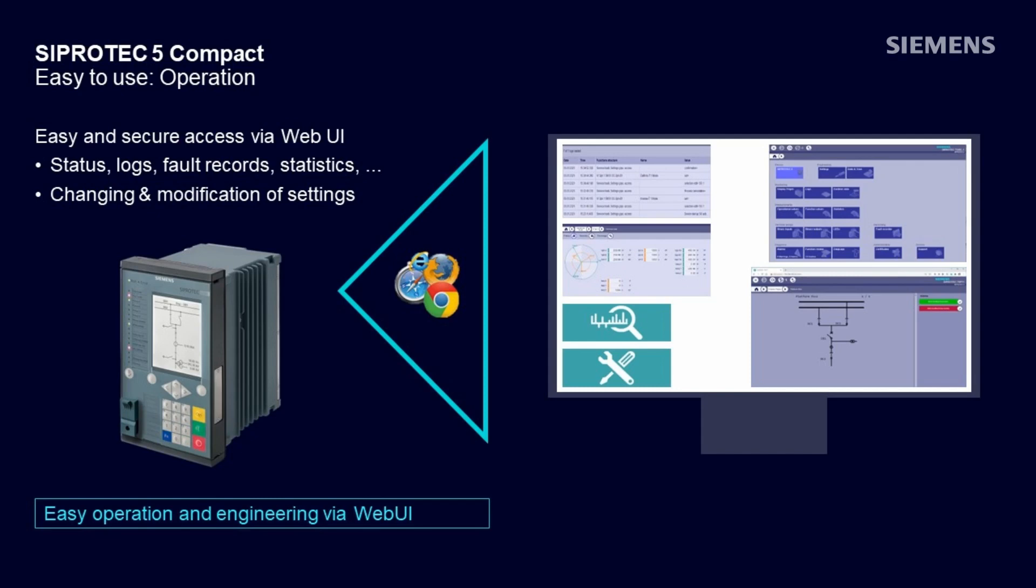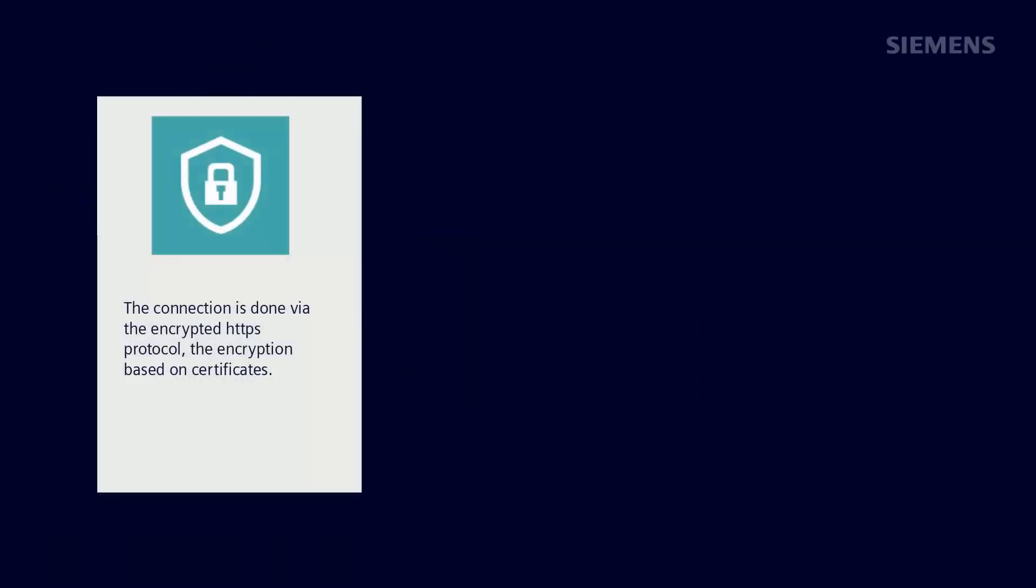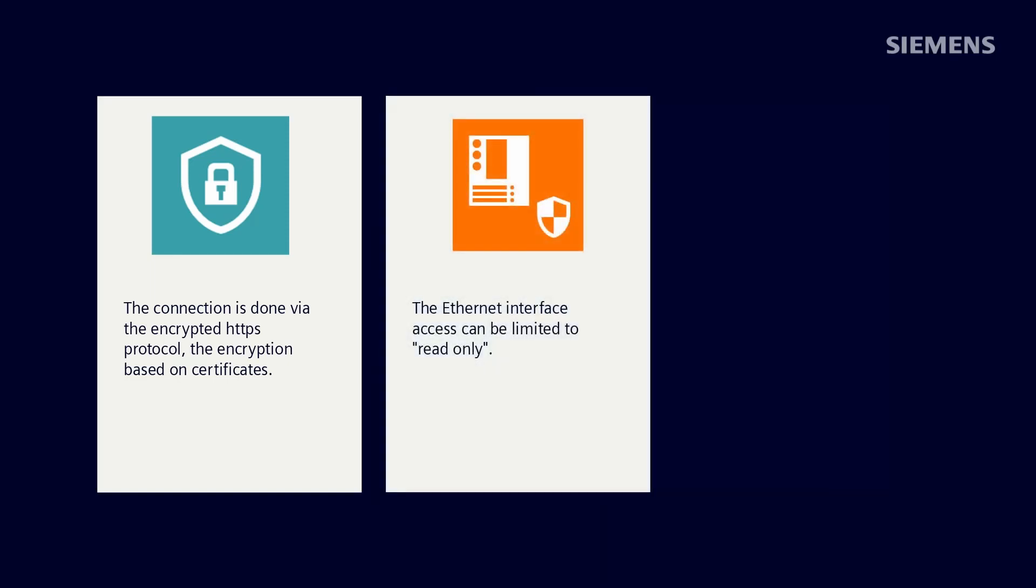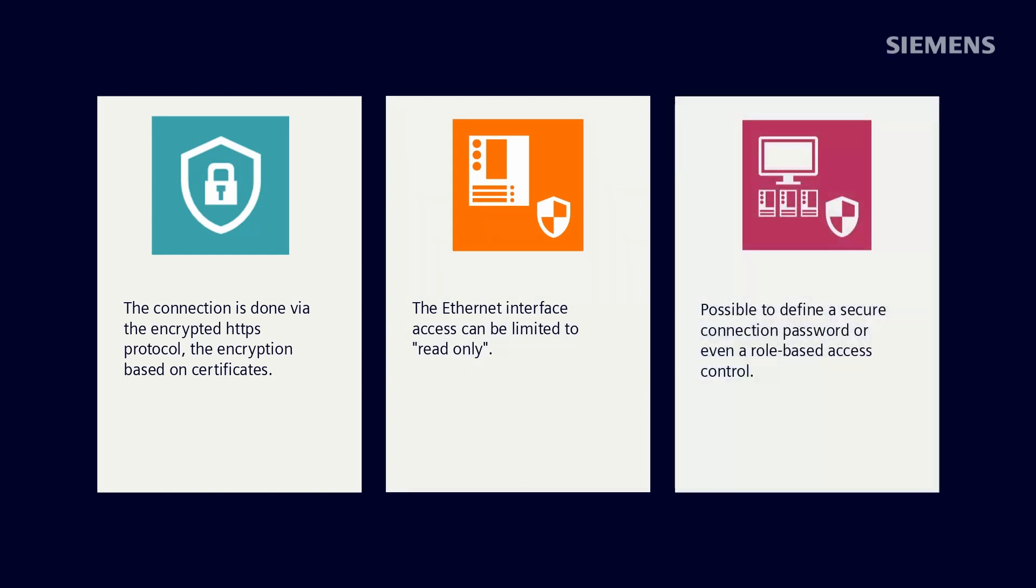Very important to mention is the fact that this access considers all cyber security requirements. The connection is done via the encrypted HTTPS protocol, the encryption based on certificates. The Ethernet interface access can be limited to read-only so that it's not possible to modify any settings, and it's possible to define a secure connection password or even a role-based access control.